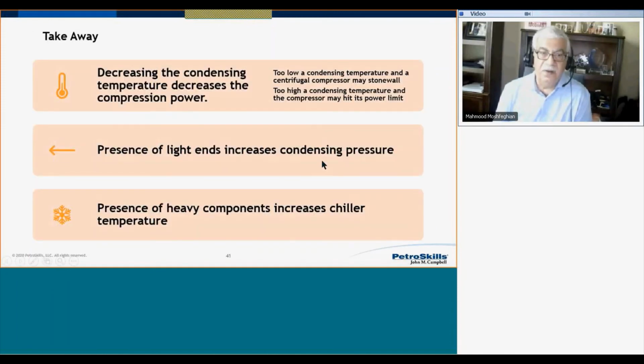A couple more takeaways from this presentation: decreasing the condensing temperature decreases the compression power. Just emphasizing what we said before, but keep in mind that with too low a condensing temperature, a centrifugal compressor may run into stonewall. Your discharge pressure will be low, your mass flow rate may be high enough to get you to sonic velocity and reach stonewall. And with too high a condensing temperature, the compressor may hit its power limit. This may happen during summertime when condensing temperature increases.